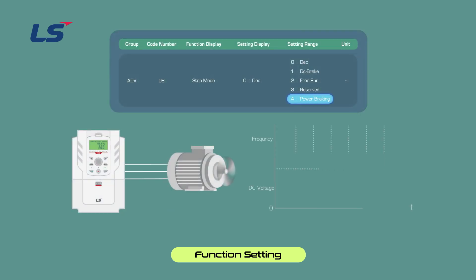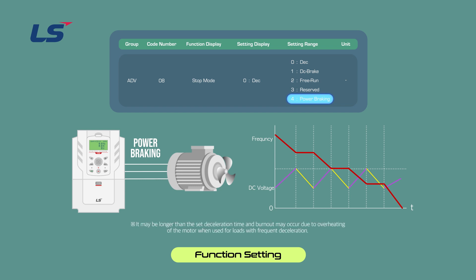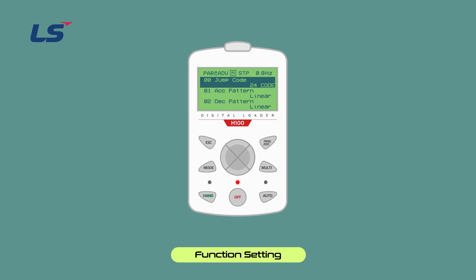Power Braking stop method adjusts the deceleration slope or accelerates again to reduce regenerative energy when the AC drive DC voltage rises above a certain level due to motor regenerative energy. It can be set and used when a short deceleration time is required without a separate braking resistor and braking unit. Note that the deceleration time may be longer than the set deceleration time, and when using it for a load that frequently decelerates, damage may occur due to motor overheating. When you press the Enter key in ADV8 stop mode, use the direction keys to move to number 4 power braking and press the Enter key to complete the power braking setting.